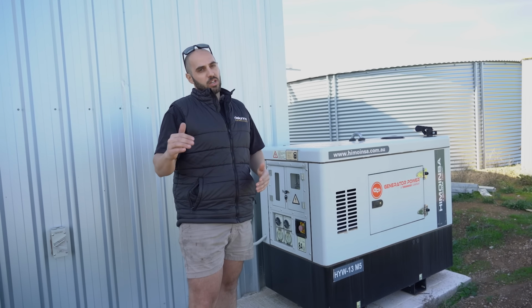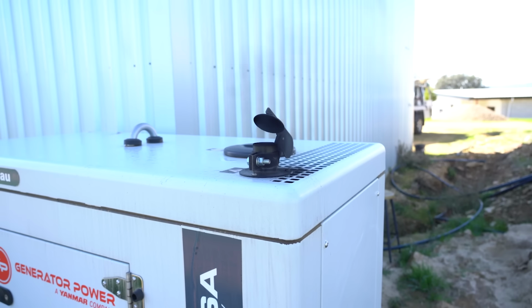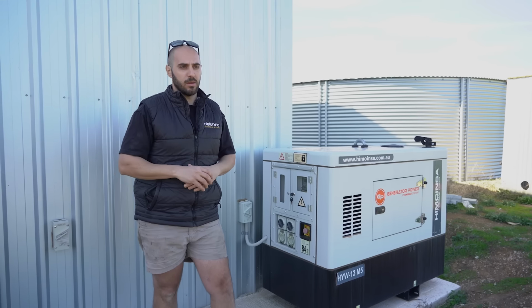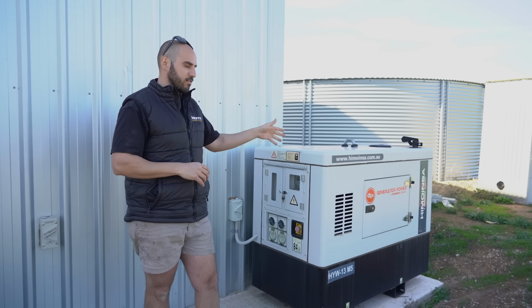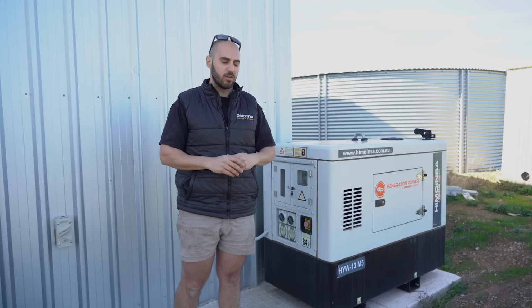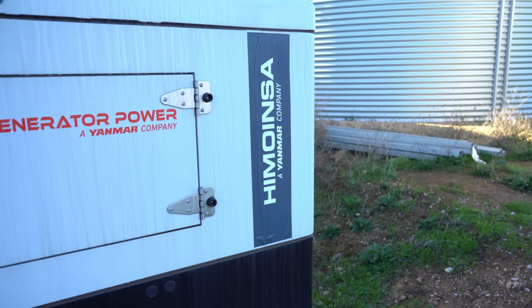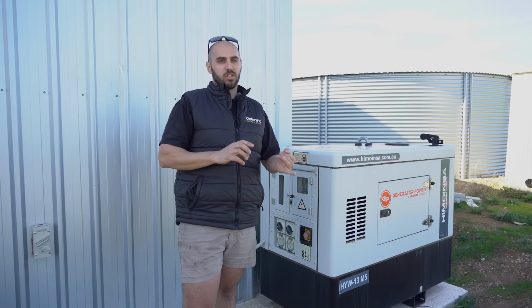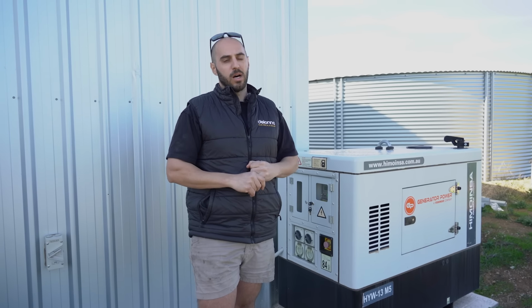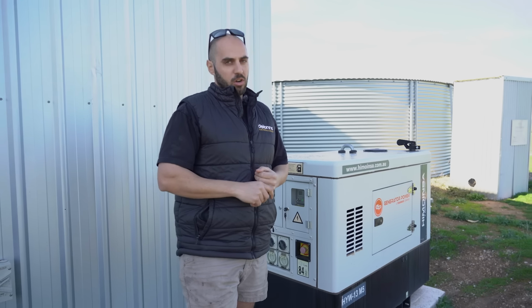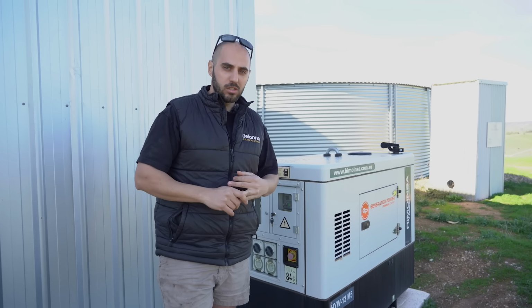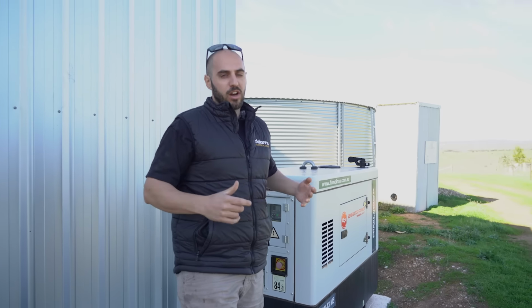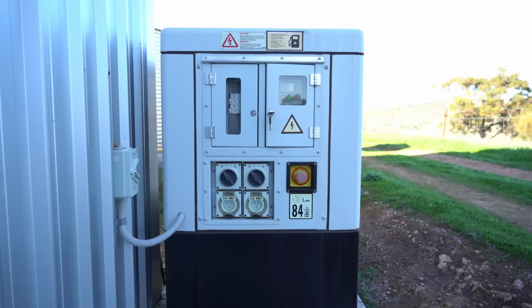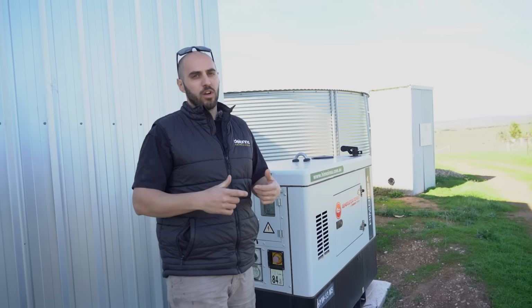When the batteries get to a certain state of charge, the Jenny will auto start. It's really important in off-grid setups, especially with higher loads, to have a generator in general. It's able to start not only when you've got not a lot of storage left, but also when you've got high demand. If for whatever reason the Quattro or Multiplus can't support the loads, we can set it up so the generator auto starts to help offset some of the load coming from your inverter charger.